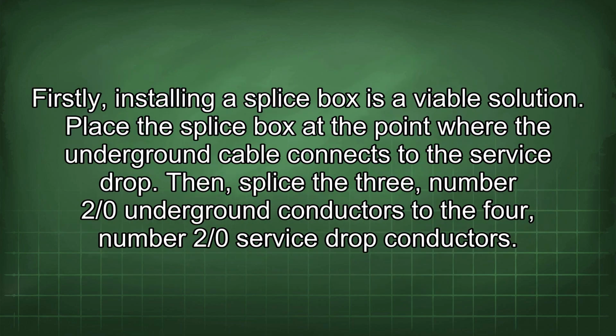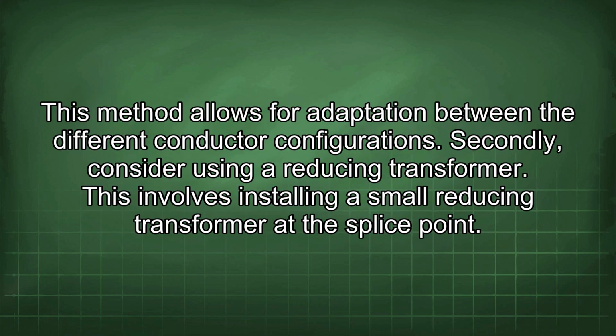Firstly, installing a splice box is a viable solution. Place the splice box at the point where the underground cable connects to the service drop. Then splice the 3 2/0 underground conductors to the 4 2/0 service drop conductors. This method allows for adaptation between the different conductor configurations.